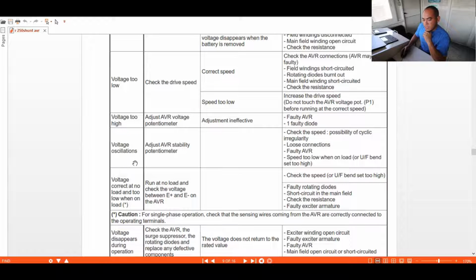Okay, so for voltage oscillations, adjust the stability potentiometer. Oscillations means fluctuations, so just adjust the stability potentiometer, and you have to check the speed and the possibility of cyclic irregularity. If there is also hunting of your engine, it will also affect your voltage, because the engine is the one that drives your alternator, so if the engine is unstable, it also affects your voltage stability. Okay, so loose connections, faulty AVR, speed is low on the load. These are the things you are going to check and monitor during your troubleshooting.